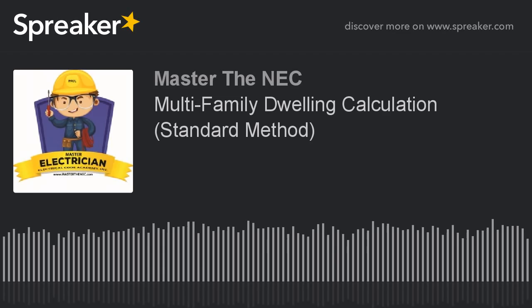I need to determine my general lighting and receptacle loads, because I've got 3 little steps to do here where I'm going to apply some general lighting and receptacle demand factors, and it's a good thing, for diversification. I have to come up with the values to apply these demands to for the general lighting and receptacle loads that are allowed in 220.12.